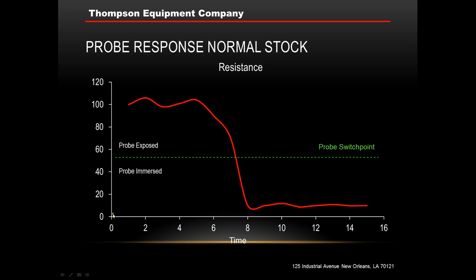The sensitivity would basically change the scale — currently from 0 to 120 — taking it from 0 to 240, or 0 to 1,000, 5,000, whatever. This is what probe resistance looks like at normal stock conditions. You would have a high value, typically a couple hundred or something like that, with some variability, until the filtrate actually hits the lower probe. When that filtrate hits the probe, the resistance drops to a low level — often 0 or 1 — and that's pretty typical for a normal condition.